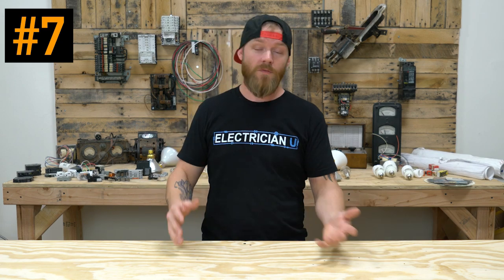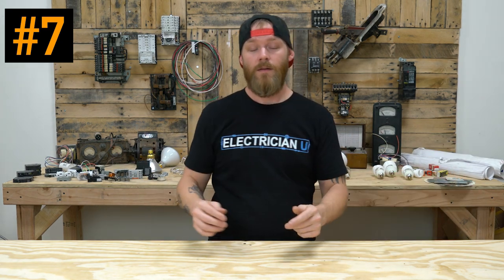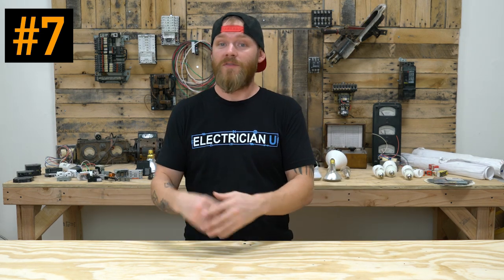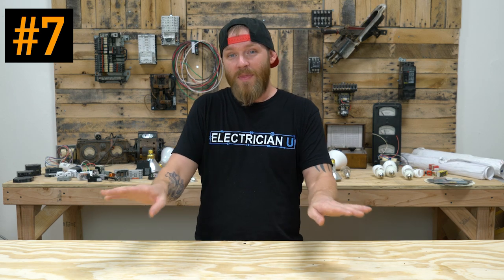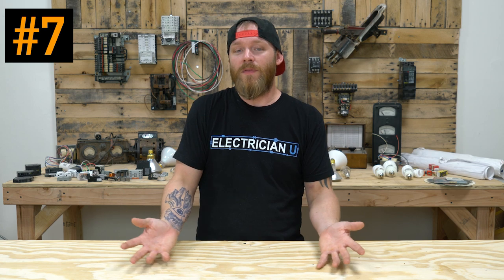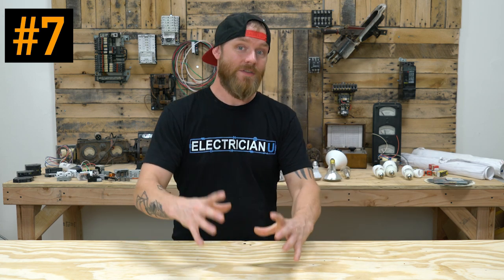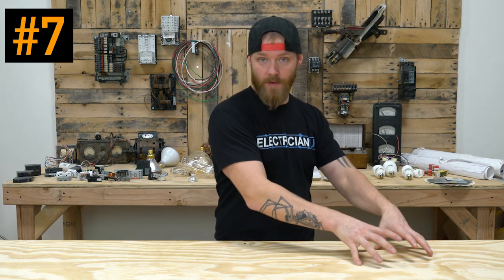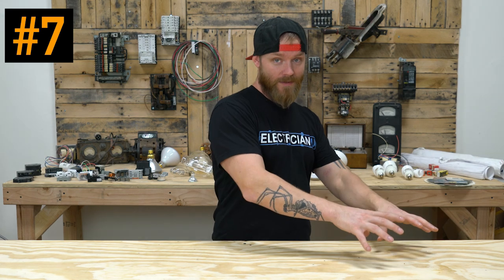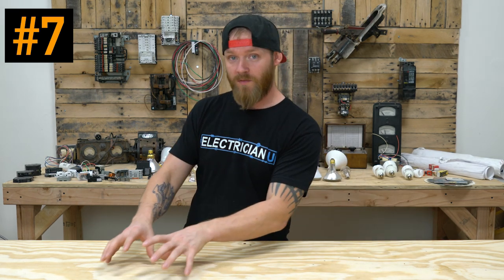So we call breakers and fuses overcurrent protection devices. And then there are overloads for motors and things like that. They're two completely different things, but they both relate to each other. And one thing that might help to think about is an overload situation, an event, can cause overcurrent. It can cause too much current to flow. But an overcurrent cannot cause an overload.